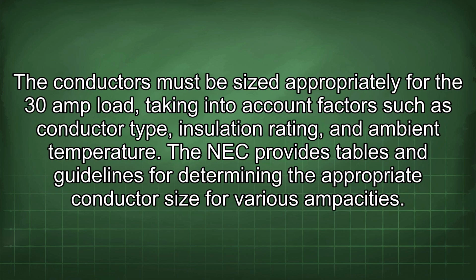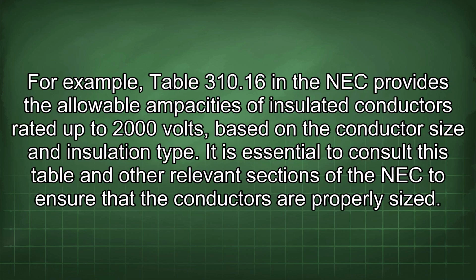The conductors must be sized appropriately for the 30-amp load, taking into account factors such as conductor type, insulation rating, and ambient temperature. The NEC provides tables and guidelines for determining the appropriate conductor size for various ampacities. For example, Table 310.16 in the NEC provides the allowable ampacities of insulated conductors rated up to 2000 volts, based on the conductor size and insulation type.